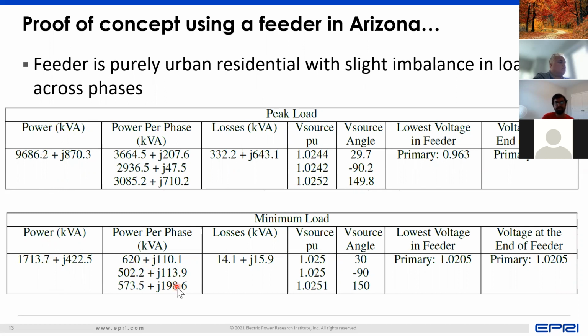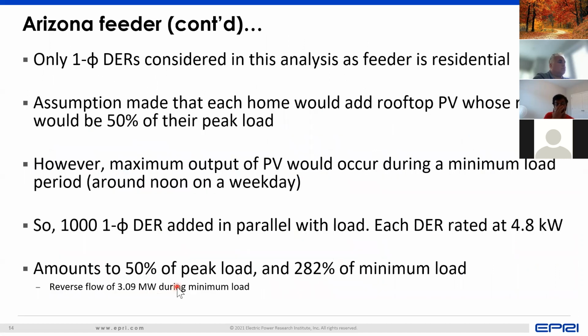And what we assumed in this analysis was that because the feeder is purely urban residential, most of the DER is going to be residential, which means single phase. We made an assumption that each home in the feeder would add a PV panel whose rating would be roughly 50% of their peak load, because that would be based upon the available rooftop space, the orientation towards sun, the inclination of the roof, and things like that. And then basically averaging them across all the loads also.